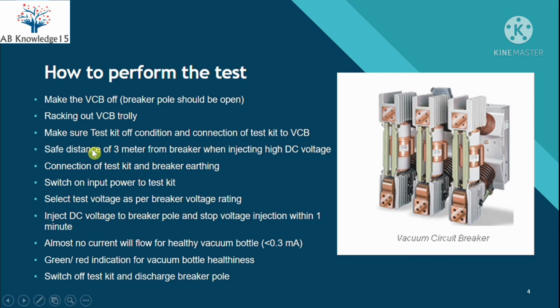While the test is running, keep a safe distance of 3 meters from the breaker while injecting the high DC voltage. This test kit injects high DC voltage, so keep a distance of at least 3 meters from the breaker for safety. Now connect the test kit earthing and breaker earthing to the earthing bus bar so that any discharges are carried to the earthing bus bar.